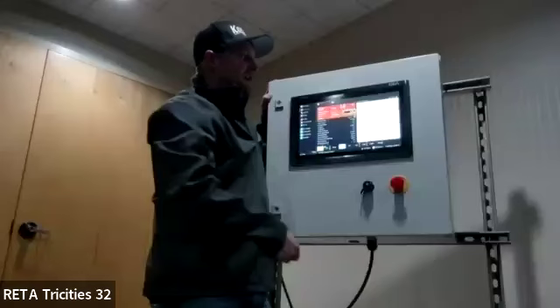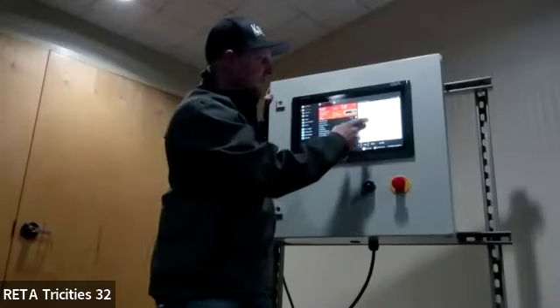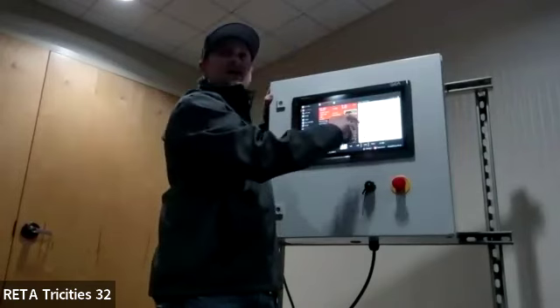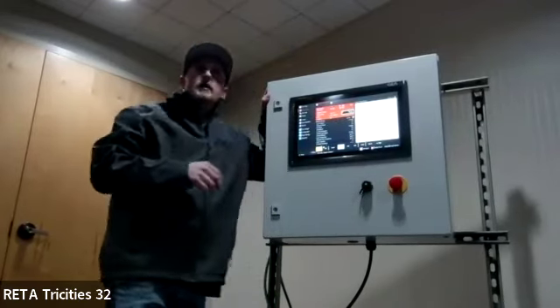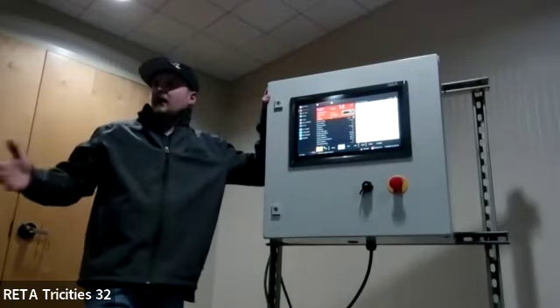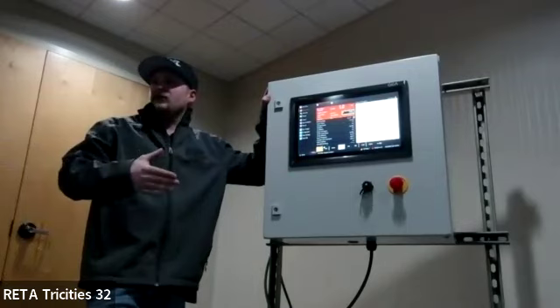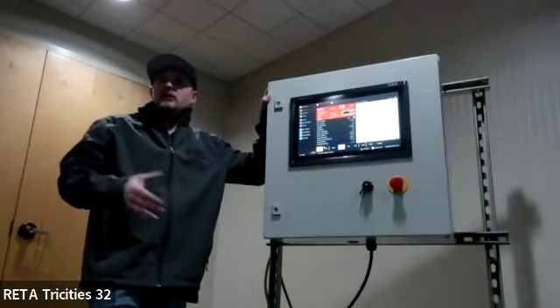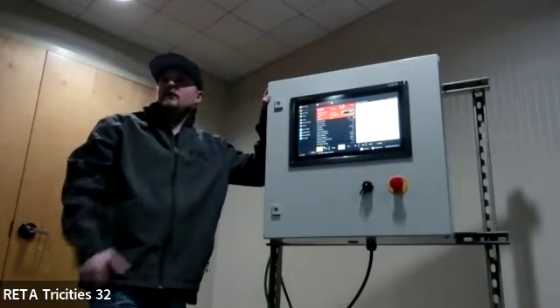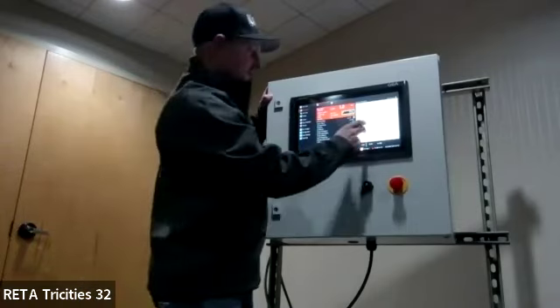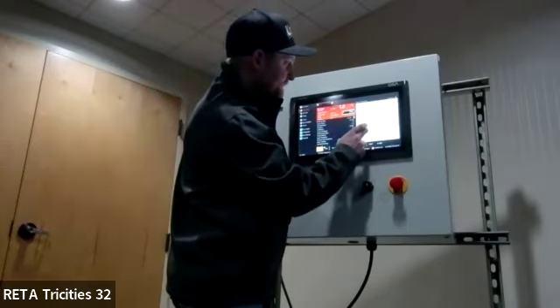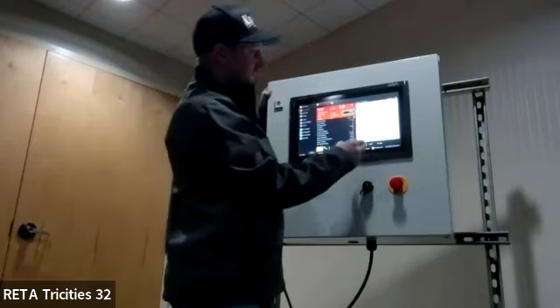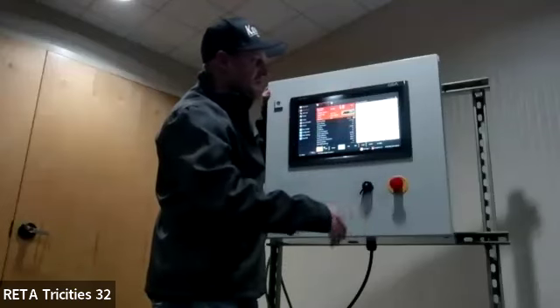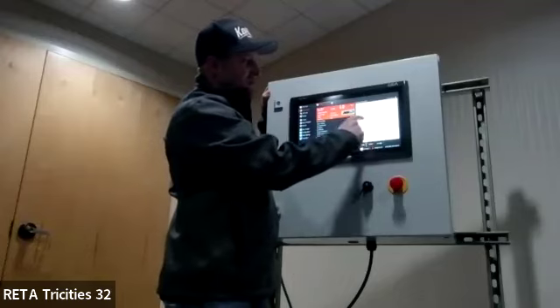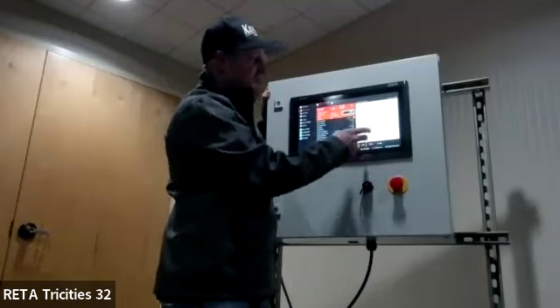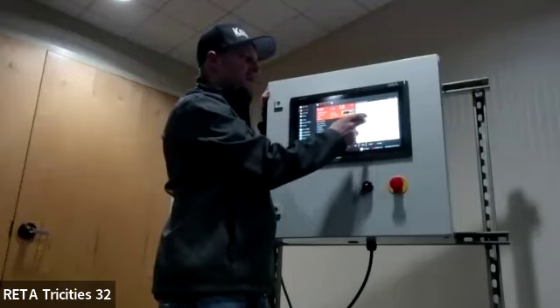Here's motor information. It's going to tell you how many starts the motor had. Runtime hours for the motor, and that is also editable. So let's say you put a new motor on and you want to reset the hours to 0, but you want to keep your compressor hours set at 100,000, whatever they're at. You can change compressor or motor runtime hours. It's not an accumulative. This can show if you want to see your kilowatt demand metering ratio, all that stuff. You can set that up with the motor nameplate voltage, nameplate kilowatts and horsepower, and it'll give you an estimated usage.